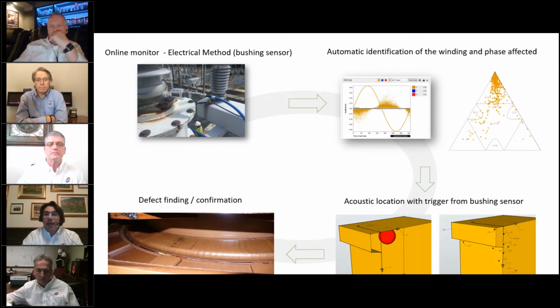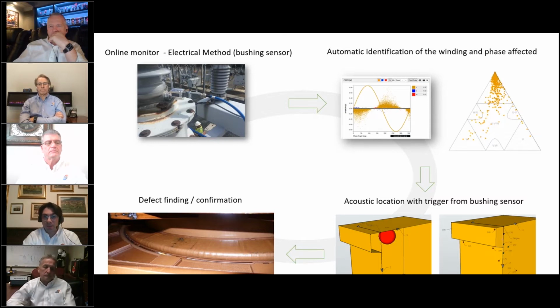Now, if you don't have the information that there is a partial discharge, in which winding and in which phase, you might end up spending a lot of time doing this acoustic location. So the best practice we see, and the main use of these sensors, is in making an investigation and locating the source in a second stage, when you already know that there is something.